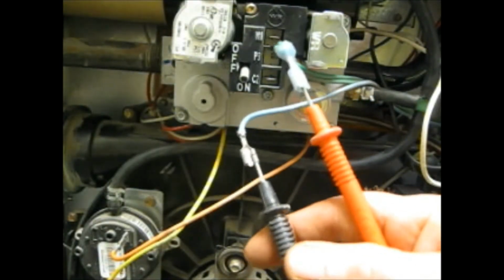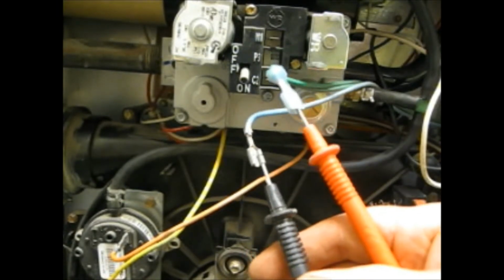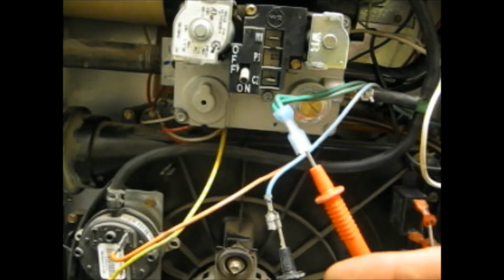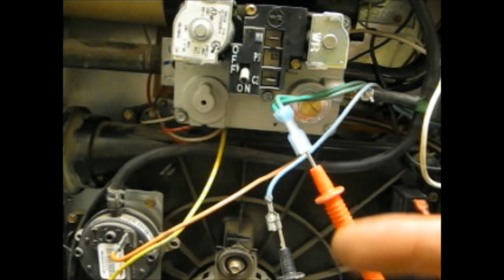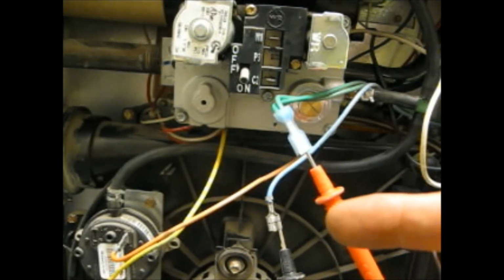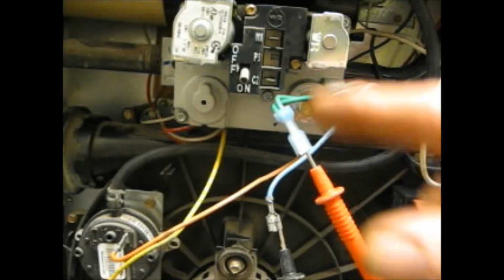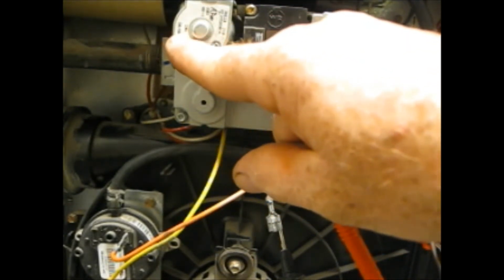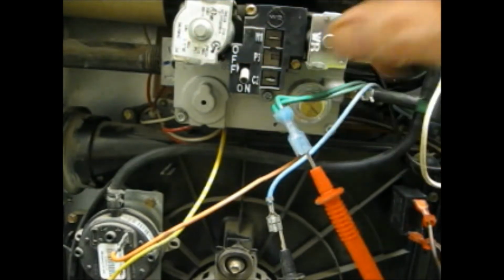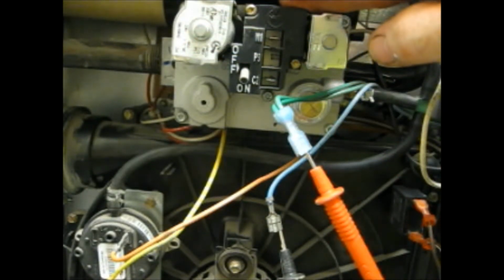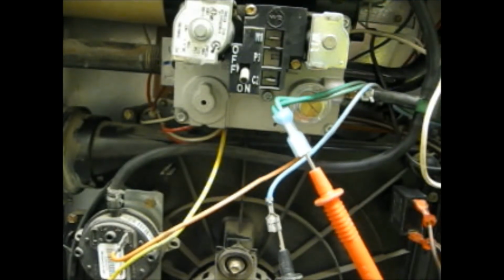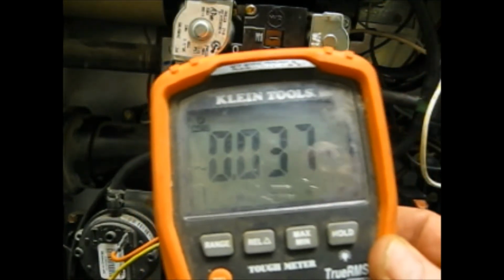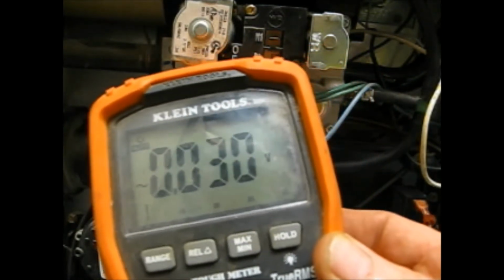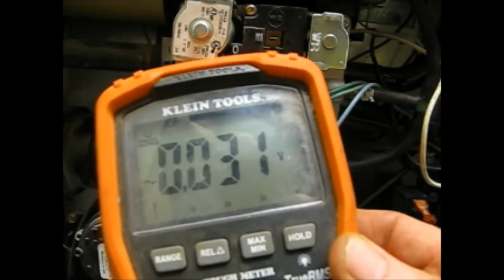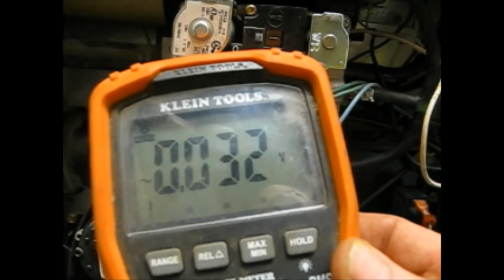Okay, we're all hooked up to our voltmeter for the gas valve. Now, in our previous test, we were looking for 120 volts on the hot surface igniter, but in this case we're only looking for 24 volts. As you can see right here, it's kind of small, but it says 24V. So the gas valve only runs on 24 volts, so that's the voltage that we're looking for. So if you can take a look right now at our meter, this is like 3/100th of a volt. That's a stray voltage, but 24 is the magic number.